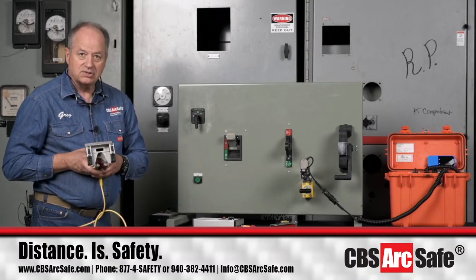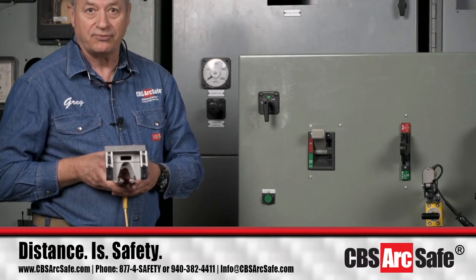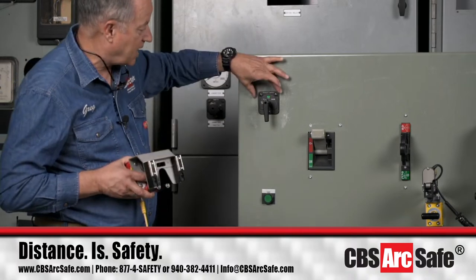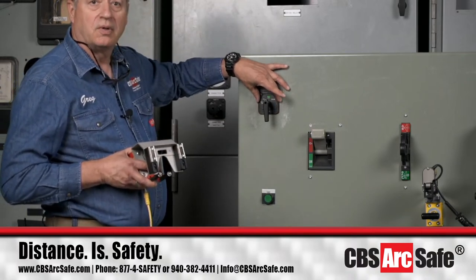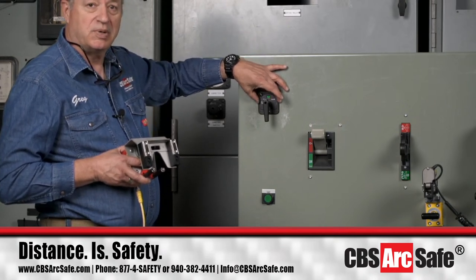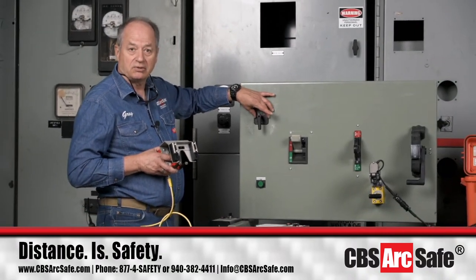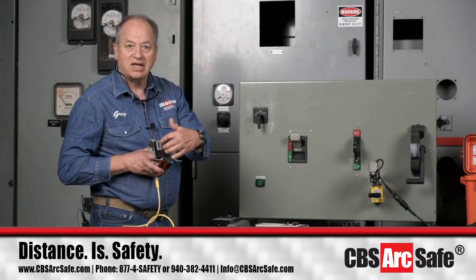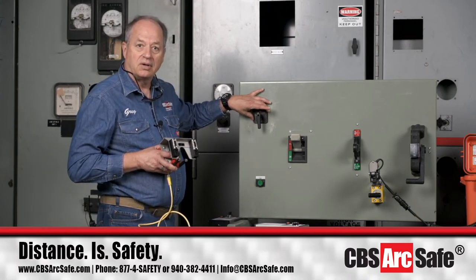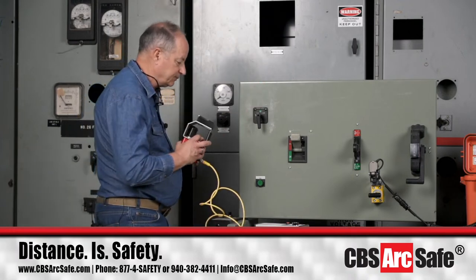Now, these come in CS01, CS02, CS03, CS04, CS05. What changes is both the shape or the size of the switch face right here. So if you were to compare this Electro Switch or a GE switch like an SB1 to a Westinghouse W2, which is narrower, you can't use the same restrictions around the face. So you have to have actuators based upon the geometry of this switch face to work properly.